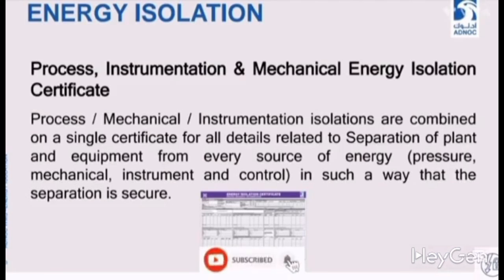Pressure, mechanical instrument and control. If we have closed any valve with mechanical and electric control, it will also be on this. If we need to do blinding somewhere, if we manually close the valve, it will also be on this. If we have done mechanical isolation with the process and disconnected or bypassed something in the instrument, its control will also be on this single permit, in such a way that the separation is secure, and it will be ensured with this permit that any energy separation blockage or stoppage will be verified, ensured or secured according to this permit.